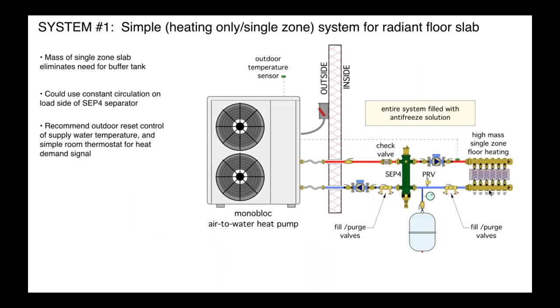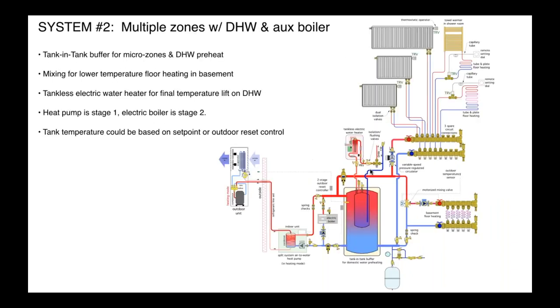Real quick, system examples. I mentioned workshops as an example, service garage. You don't have to be elaborate. Very simple. It's a single zone, high mass radiant slab supplied through a hydraulic separator, supplied by, in this case, a monobloc heat pump. We're putting antifreeze in the whole system. Putting the hydraulic separator gives us all our air, dirt, magnetic particle separation. It separates the pressure dynamics of the heat pump circulator from the distribution circulator. It lets you do constant circulation if you want over here, and basically just turn the heat pump on and off when we need heat input. So there's a real basic, simple system that would work well in a slab-on-grade building, okay?